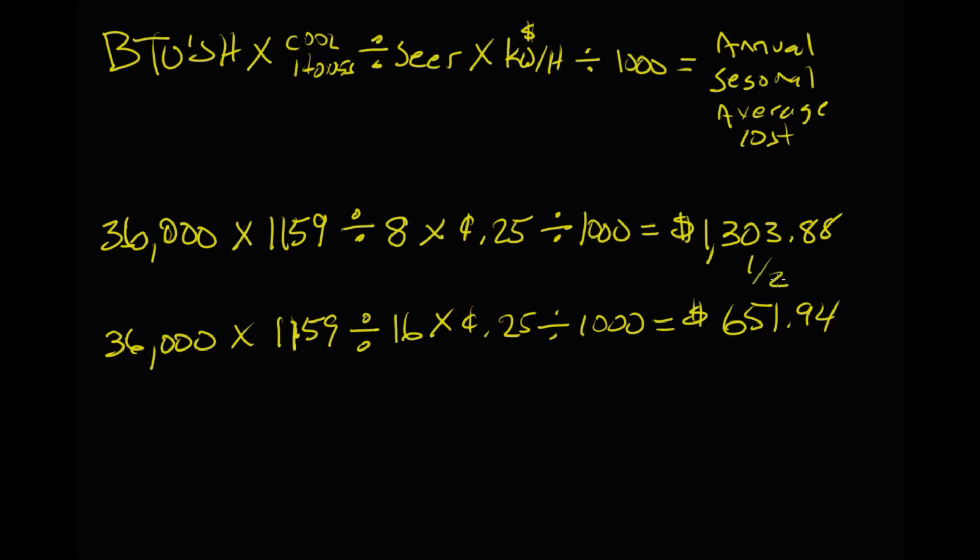That is half of the $1303.88. Remember how I said that this is the 8 SEER. Whenever you double it, or if you go from an 8 to a 16, you're actually consuming half the energy. So it's costing half as much to run that piece of equipment. If you take it one step further and you subtract the amount from what you were doing, how much are you actually saving? Well, you're saving $651.94 every season by just changing this piece of equipment out to a 16 SEER.